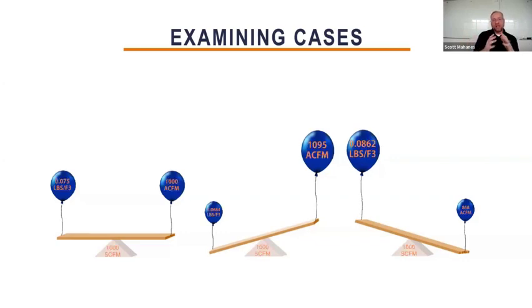And so what's interesting is if you see with these numbers put in here, that if you're at standard density conditions and your level on the left here, you can see that the 1,000 CFM of volume is the same as the mass flow. But if I reduce the amount of density, I've increased my volume, and the standard CFM has not changed. And the inverse of that is if I increase density, the volume has to go down.